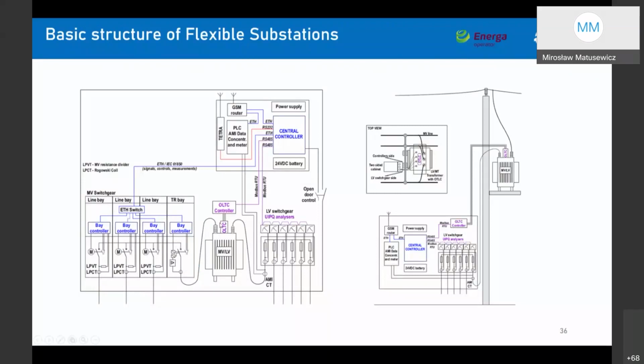The most important part for all these substations is a transformer with OLTC and its controller. Also similar is the low voltage switchgear. What's not typical is that every field line feeder is equipped with a power network analyzer, so we can control the voltage, the current in each feeder, and other network parameters like harmonics, everything we can measure there.